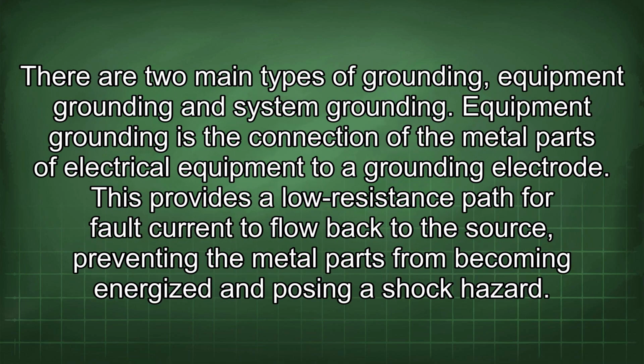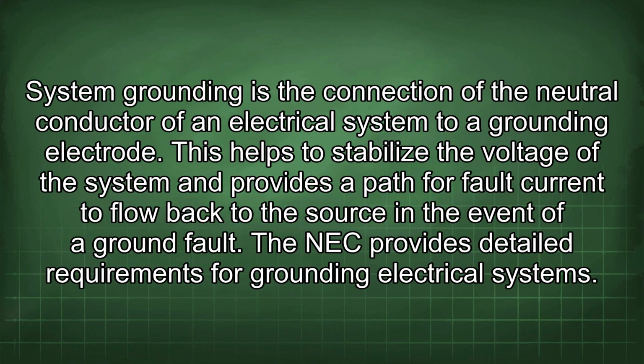There are two main types of grounding: equipment grounding and system grounding. Equipment grounding is the connection of the metal parts of electrical equipment to a grounding electrode. This provides a low-resistance path for fault current to flow back to the source, preventing the metal parts from becoming energized and posing a shock hazard. System grounding is the connection of the neutral conductor of an electrical system to a grounding electrode. This helps to stabilize the voltage of the system and provides a path for fault current to flow back to the source in the event of a ground fault.